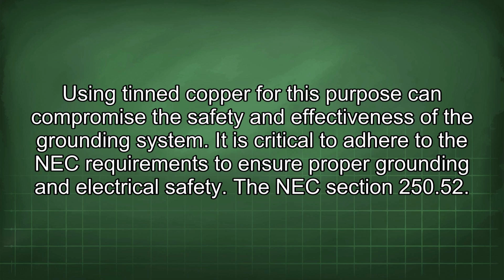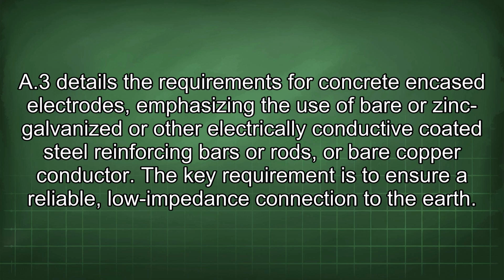The NEC Section 250.52(A)(3) details the requirements for concrete encased electrodes, emphasizing the use of bare or zinc galvanized or other electrically conductive coated steel reinforcing bars or rods, or bare copper conductor. The key requirement is to ensure a reliable, low-impedance connection to the earth.